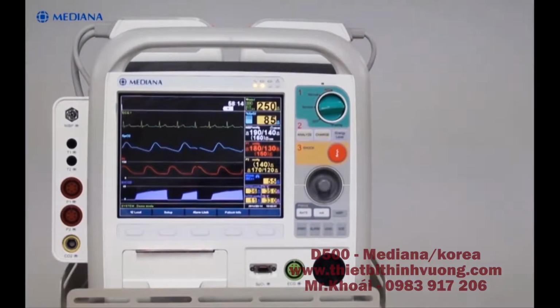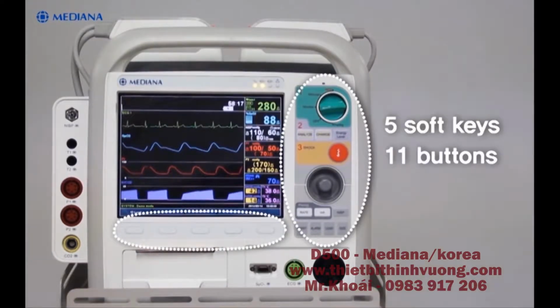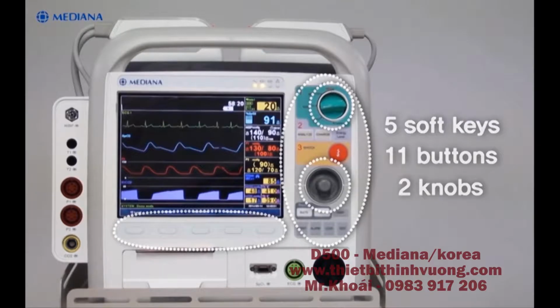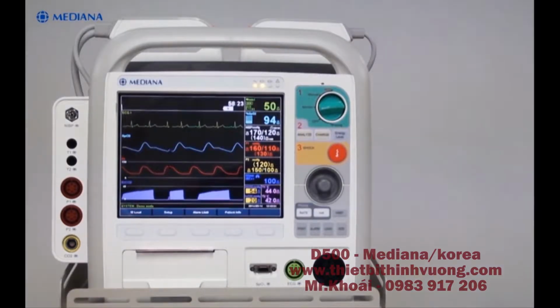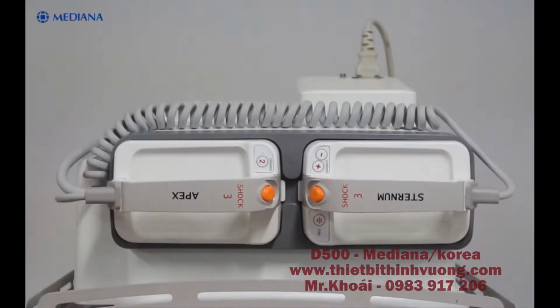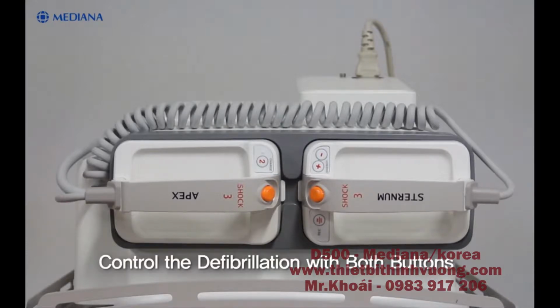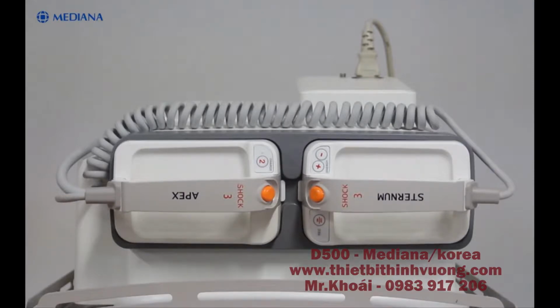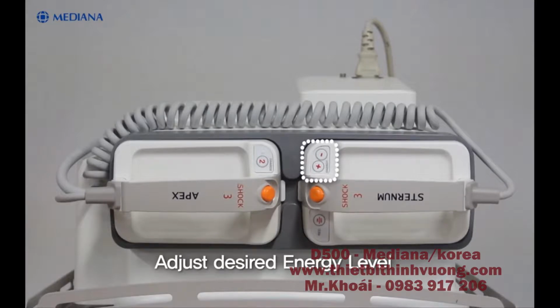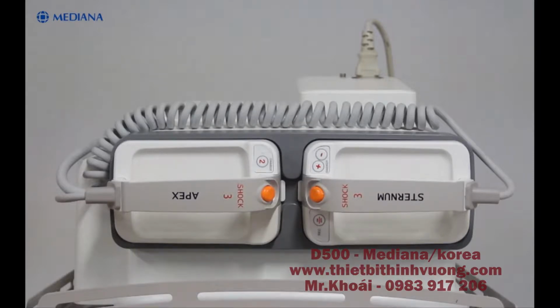Looking at the front, you can see the 5 soft keys, 11 buttons, and 2 knobs used for its simple operation. For the details of each button and its function, we will review them soon when I talk about its operation. On the top panel, you mainly see the paddles that deliver the shock and the buttons on them. One of the main advantages is that you can control the defibrillation with both the buttons on the paddle as well as the buttons on the unit. So with these 4 buttons on the paddles, you can adjust the desired energy level by pressing the plus and minus buttons, charge and deliver the energy, and finally print out measured data with the record button.